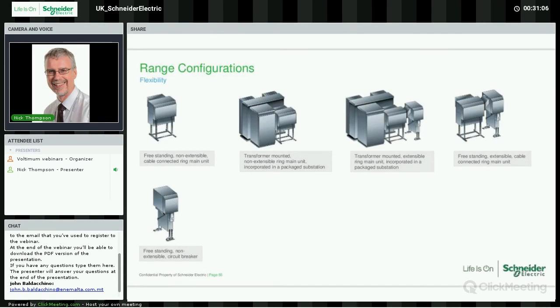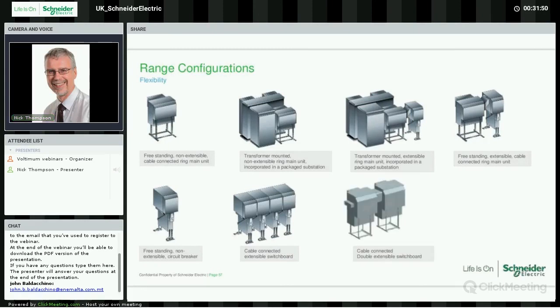A popular unit for local control of a transformer at the end of a radial feed is Ringmaster range non-extensible. You get the benefits of main circuit earthing on the main incoming cable, but also the lower fault rated transformer earthing for when you want to do maintenance on the transformer or the LV side of the transformer. You can locally earth the transformer without having to earth down from the main feed circuit breaker. Ringmaster range also comes in as an extensible version where you can make up a multi-panel switchboard. The only limit there would be the current rating of the bus bar and the fault rating of the bus bars as well.